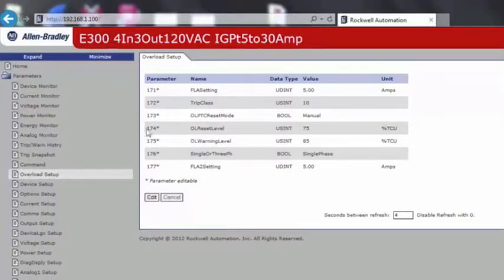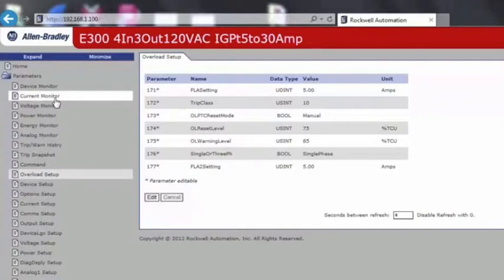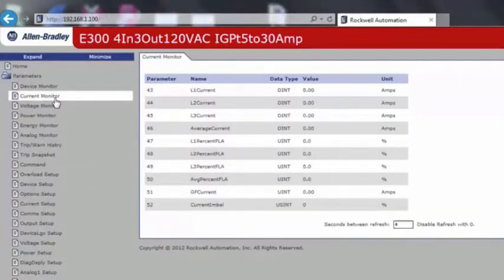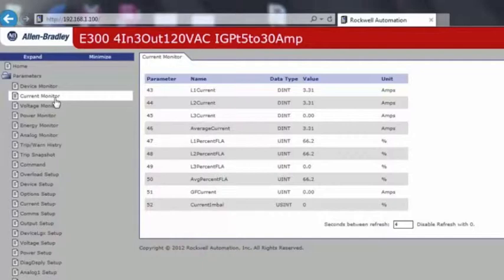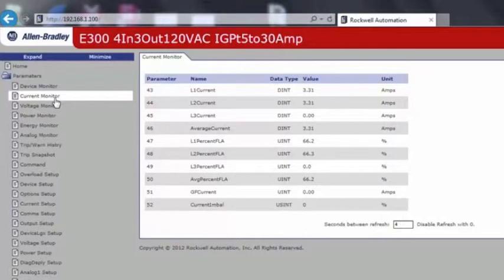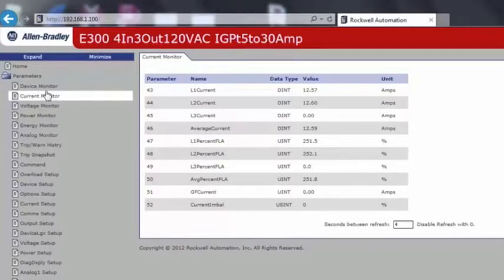Now we will demonstrate an actual Overload Trip. The motor normally operates at 3 amps. We have the Full Load Amperage set to 5 amps. Now we will push the motor to an Overload State. You can see that at 12 amps, we are at 250% full load amperage.